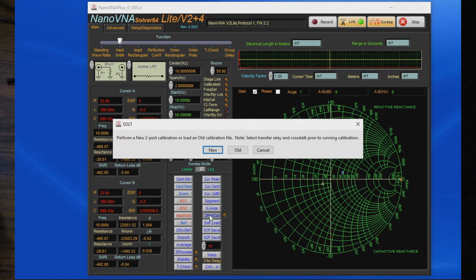So let's just go ahead and we'll load up a calibration. Again, we do that by selecting 2-port cal. And in this case, we'll load up a previously stored one. And the one I'm loading is called Lite. And this is 401 data points. It's starting at 10 kilohertz. It's going up to 50 megahertz. It's a 1-port SOLT cal. And we can see the unit has now been calibrated.